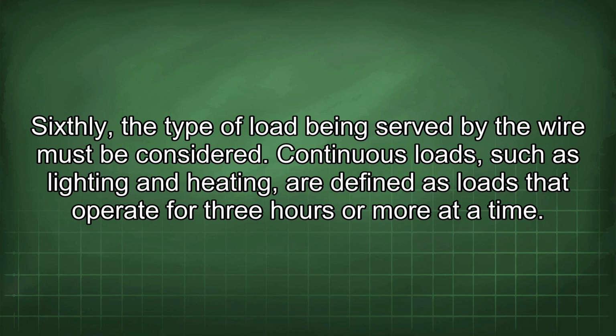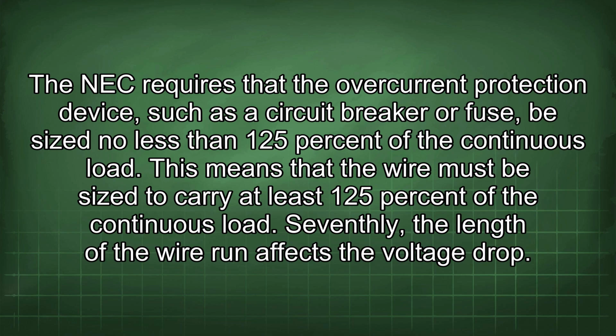Sixthly, the type of load being served by the wire must be considered. Continuous loads, such as lighting and heating, are defined as loads that operate for 3 hours or more at a time. The NEC requires that the overcurrent protection device, such as a circuit breaker or fuse, be sized no less than 125% of the continuous load. This means that the wire must be sized to carry at least 125% of the continuous load.